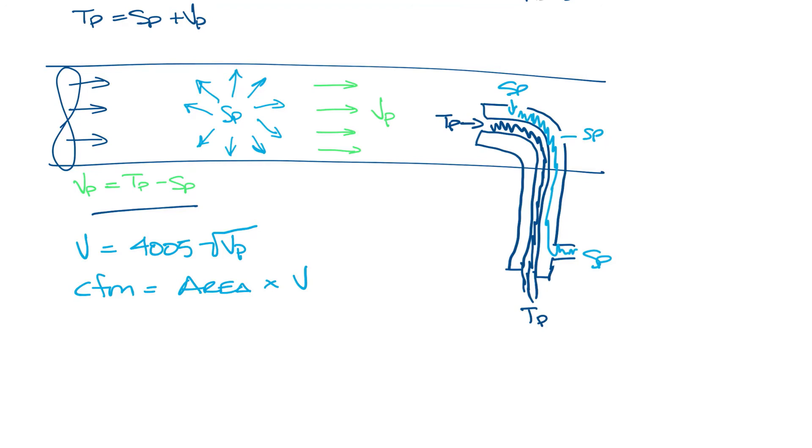Let's plug in some numbers here. Let's say our total pressure is 0.75 and our static pressure is 0.3. The velocity pressure is total pressure minus static pressure, so that's 0.75 minus 0.3 equals 0.45. So velocity equals 4005 times the square root of 0.45, and that equals 2687 feet per minute.